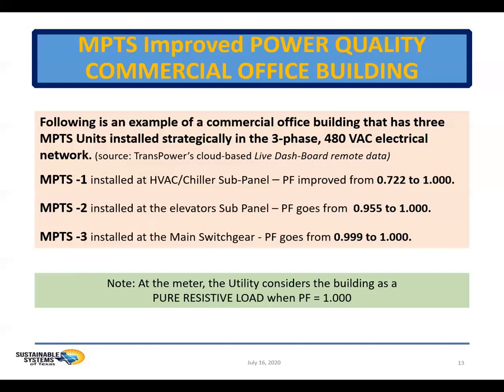It's best to install the MPTS close to the source of the problem. One MPTS unit was installed at an HVAC chiller subpanel, resulting in clean power on that subpanel. The second MPTS unit was installed at the elevator subpanel, resulting in clean power on that subpanel. The third MPTS unit was installed at the main switchgear panel, protecting the building systems from incoming utility power issues.